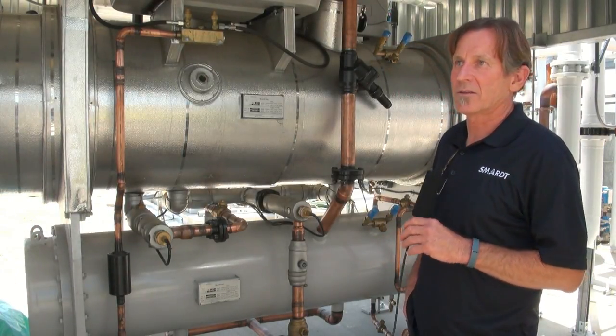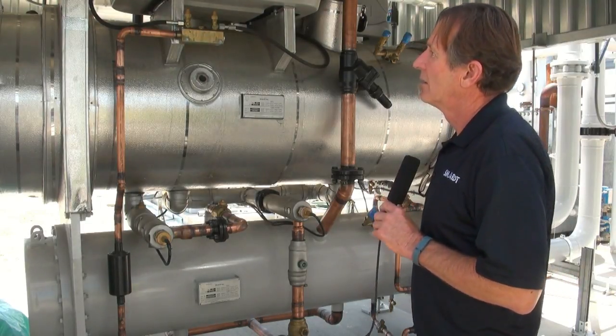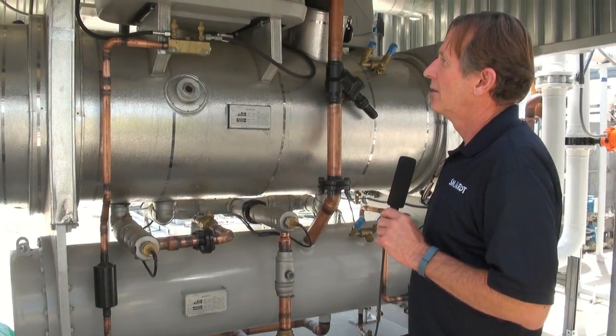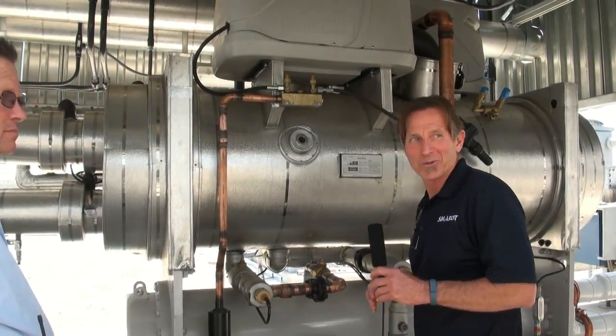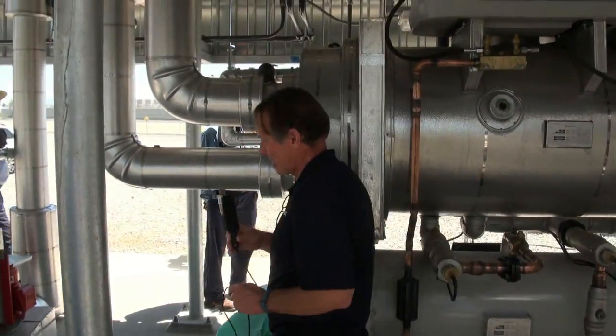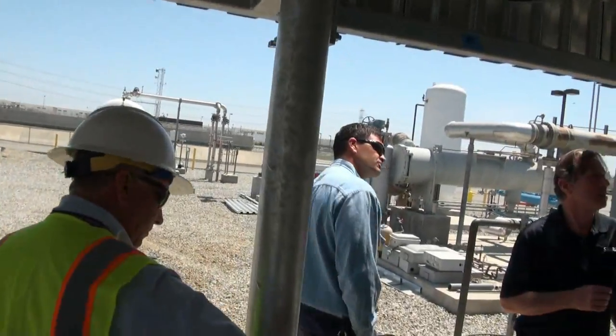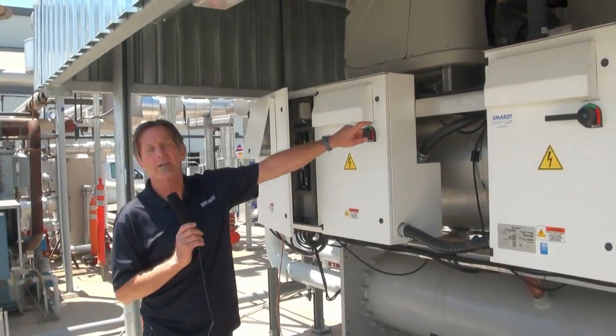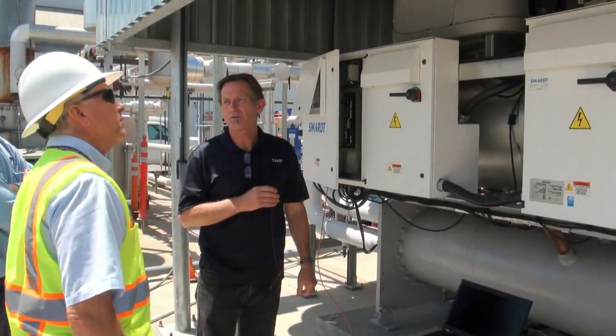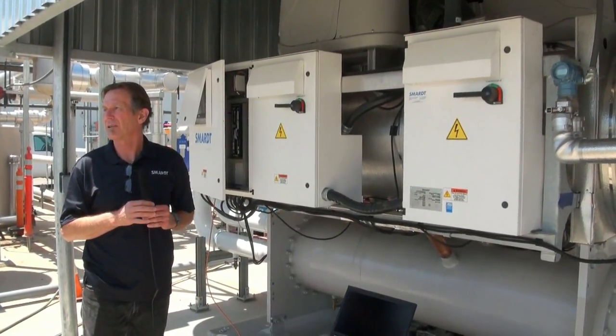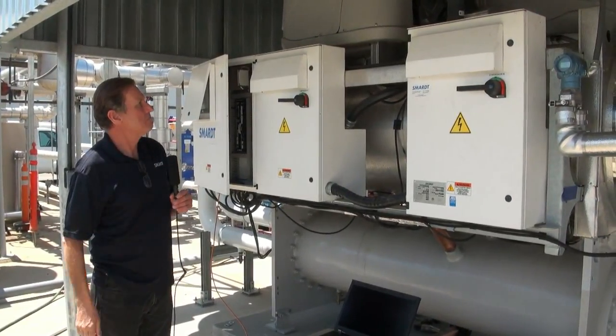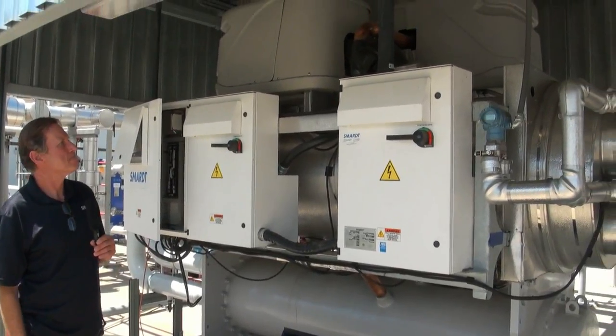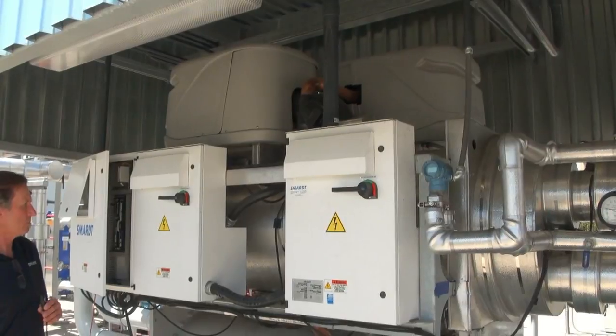Any questions on the components, guys? Anything you see? The valve. Which valve? We're walking back this way. On the suction side, is that just an isolation valve, or is it connected to... The butterfly valve that you're looking at. Yeah, the butterfly valve on the suction. That's for isolation. So you isolate the compressor from the rest of the system. It's just a 90-degree turn on that valve, and you will isolate it. Automated? No. It's an isolation valve.